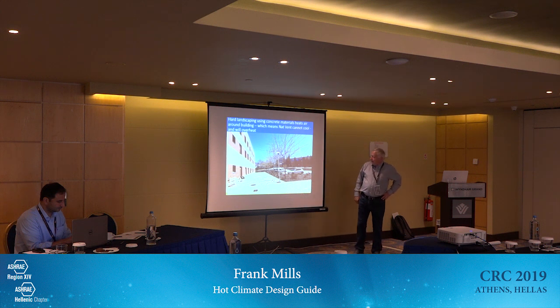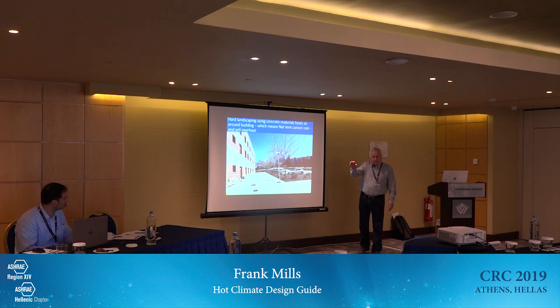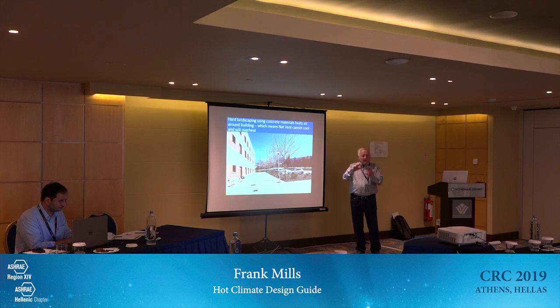So I don't know how much temperature you'd expect that to be, but I suppose if you think of Athens here, and you're walking through Athens in the summer, how much hotter is it on the street of Athens than it would be out in the countryside? 5 or 7 degrees C, you see. So if you've got the weather data for Athens, you think, oh, the summertime temperature is going to be 32, and you design the air handling plant for that. It's not, it's going to be 39.